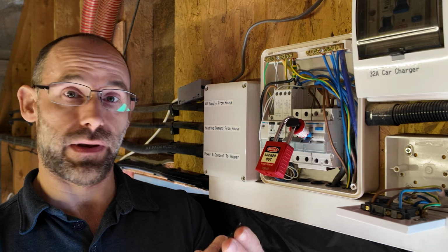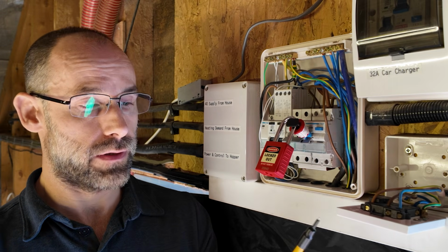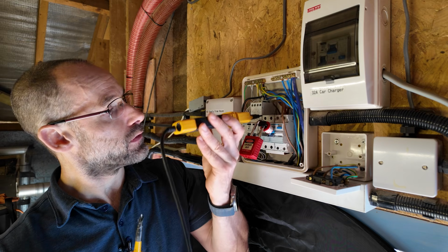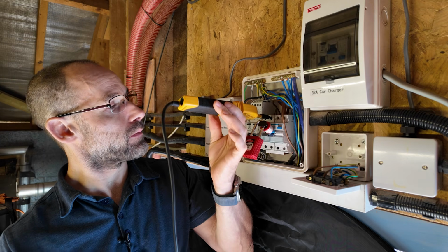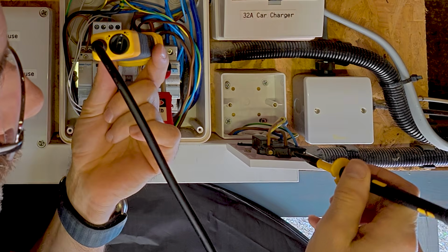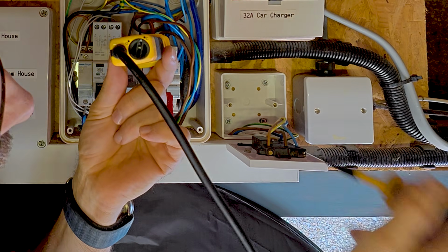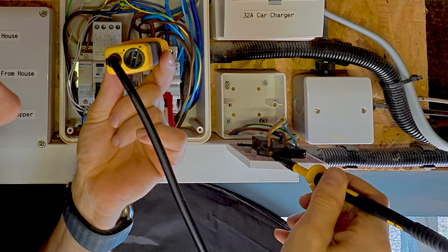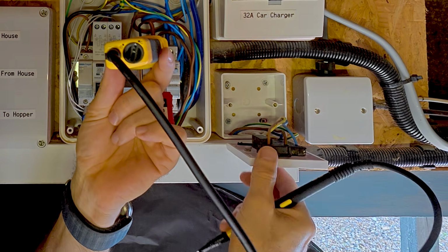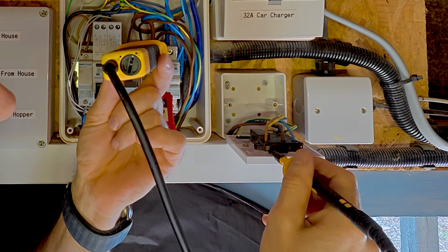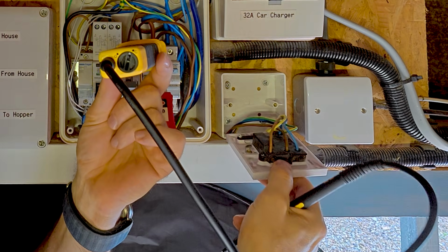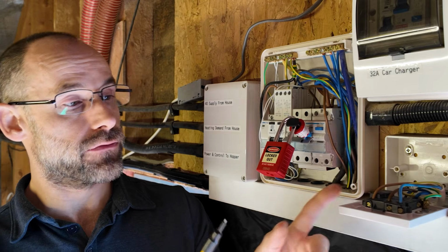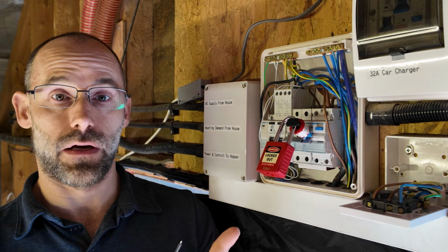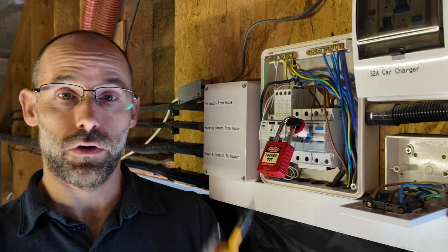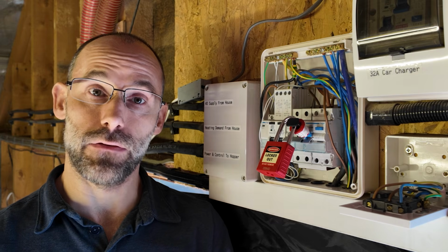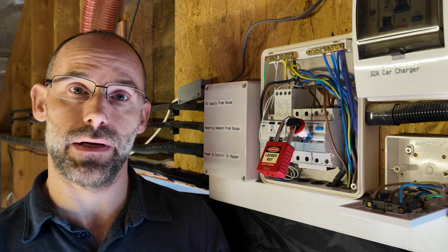Avoid outdoors, wet places, and have taken the front off your consumer unit, and you'll be all good. But I need to do this test with the front off. So what I'm doing is I'm coming to the output there, and then I'm going to just probe on the input just to check things. There you go. We get a beep, and if I come to the output, I get nothing. Now, if I toggle the switch and go to the output, now I get continuity. So what that tells me is that this switch is switching the line conductor, which is what I want. All right, cool. That's polarity in terms of switching. We'll see another polarity in a minute, by the way.